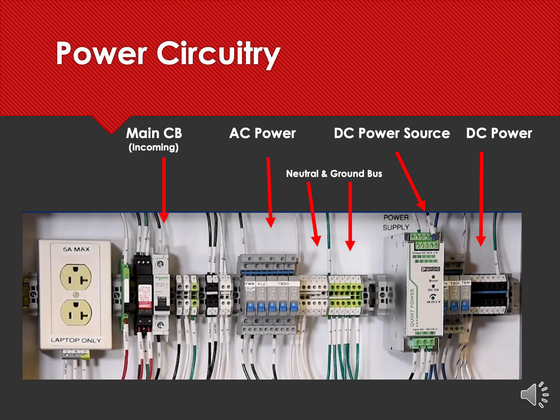Moving to the right, on the top tier here, we see the AC incoming power to the system. You'll see AC power and a red arrow pointing at a terminal block that contains all of the AC circuit breakers for this particular panel. Moving to the right of that, you'll see the neutral and grounding bus. The neutral bus with the white wires are connected together, and the green wires represent the grounding bus. Taken as a whole, from the grounding bus all the way to the circuit breaker on the left side, this is the alternating current side of the switchgear, of the control panel.